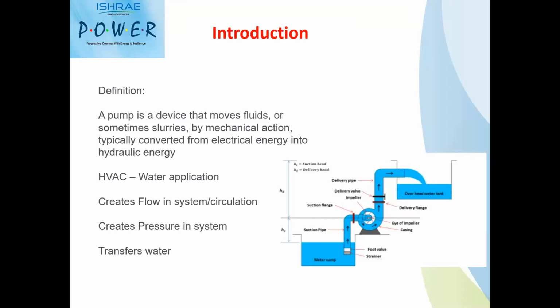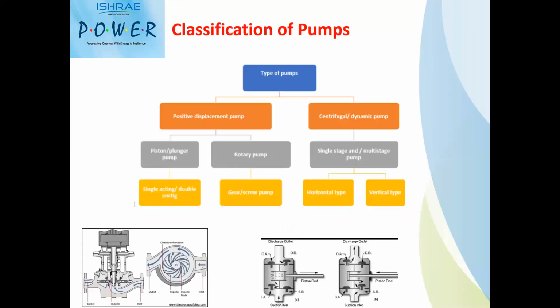And the typical terminology for HVAC: it creates flow rate, it creates pressure, and it transfers the water as well. Classification of pumps. Basically, if you see the broader classification of the pumps, we have positive displacement pumps, which have an arrangement for physical movement of the liquid through either a piston or kind of engine arrangement, where the fluid is sucked and pushed, which creates the acceleration to the liquid.